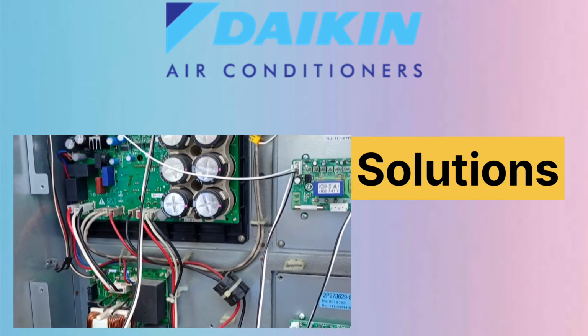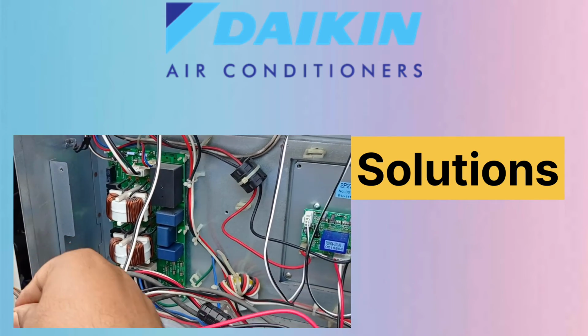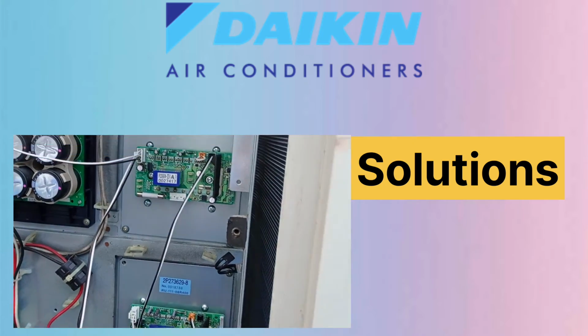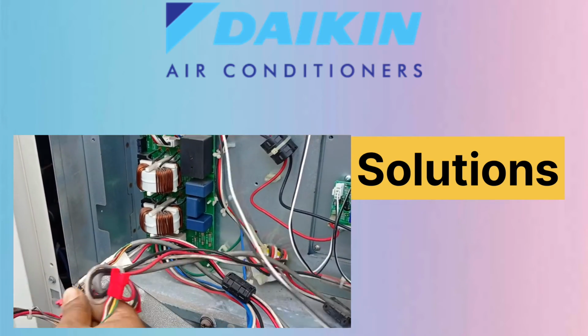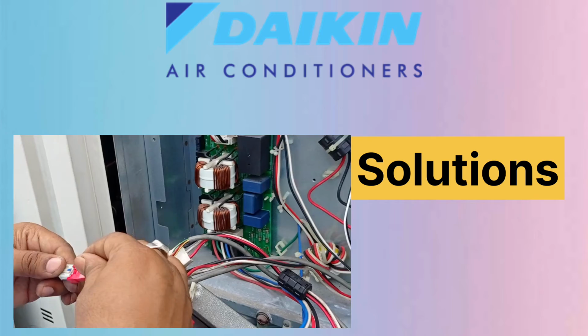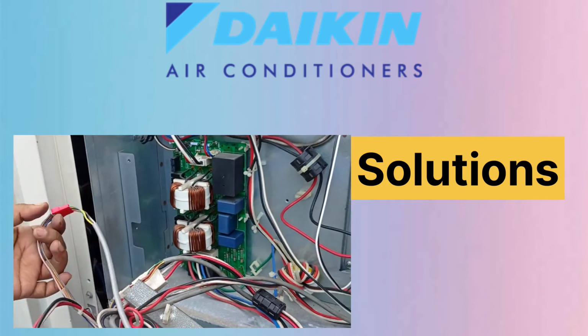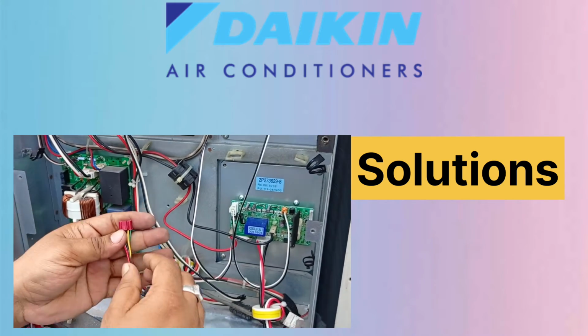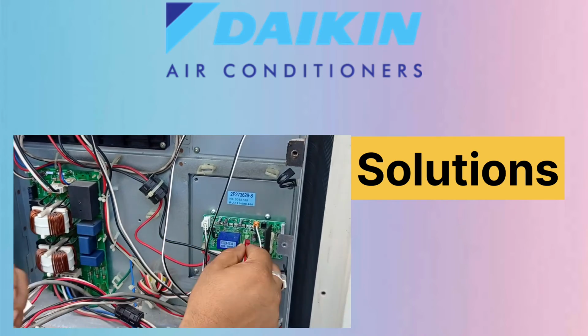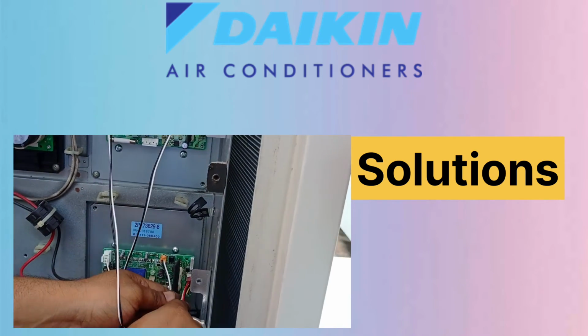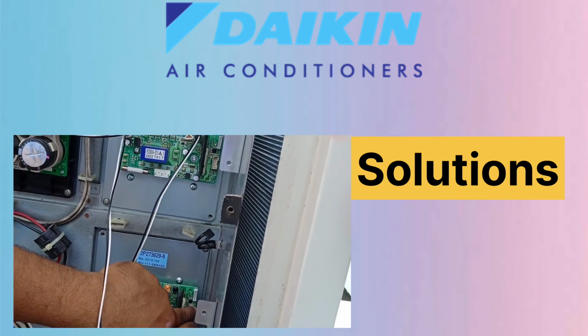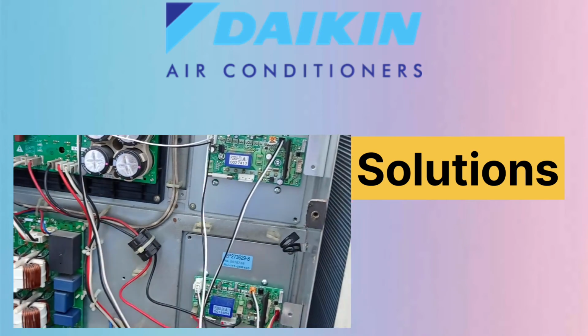Now let's talk about the solution for the error A0. The main cause of this error A0 is due to the loose connection of your terminal wire or the connectors. Make sure you connect your cable properly in the indoor terminal as well as outdoor terminal and all the connectors in your indoor as well as outdoor, and you will get the solution for the error A0.